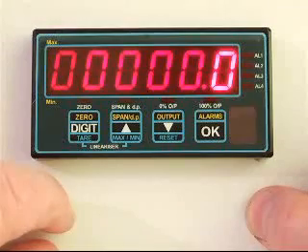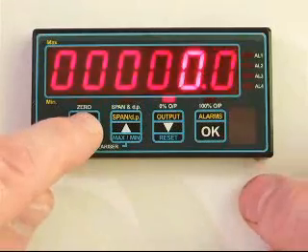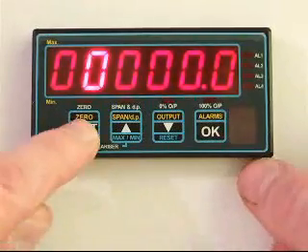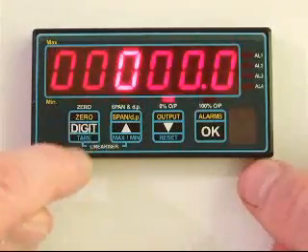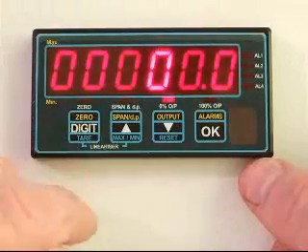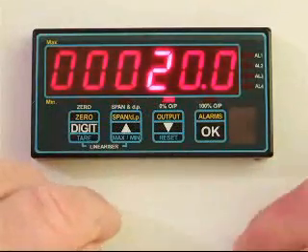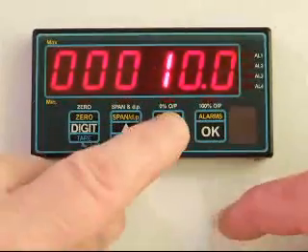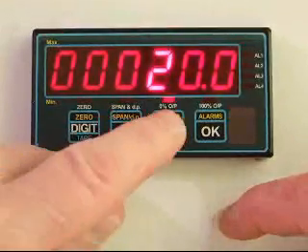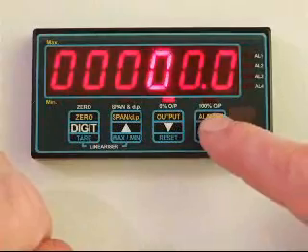and we wanted four to twenty out. We would set zero as our bottom end, and you can change this by using the digit key. So if you didn't want zero, let's say for example you wanted twenty, we'd move along to this position and use the up button to increase this digit to a two. And the down button will decrease the value of a digit. But we want zero. So with zero on the display, I press OK.